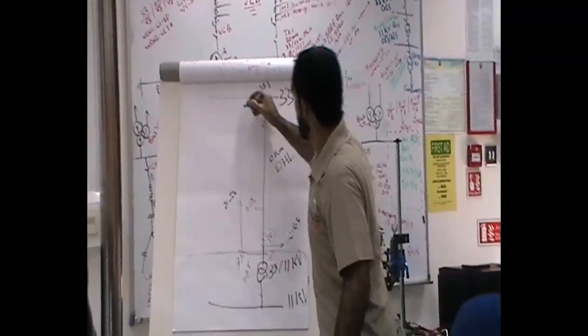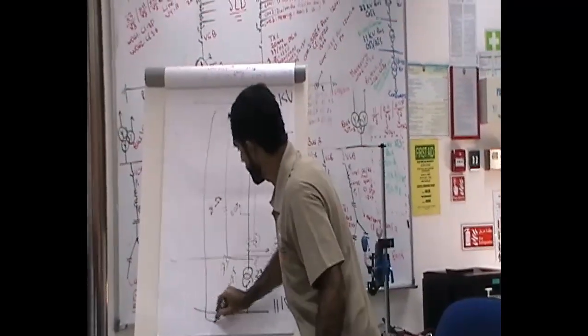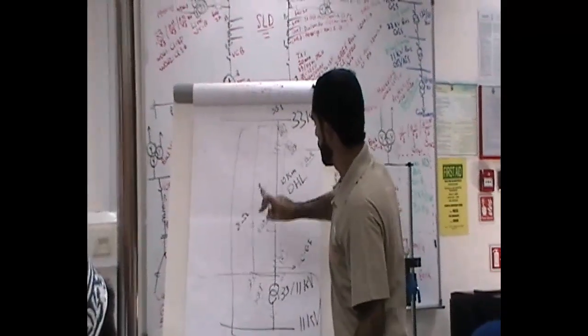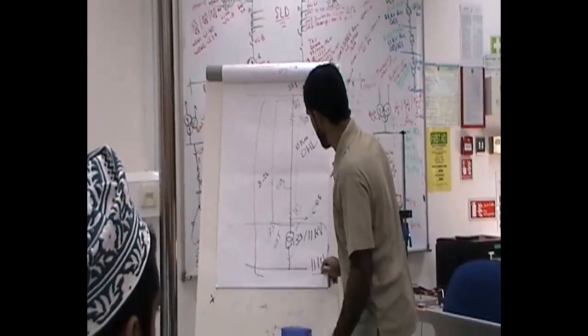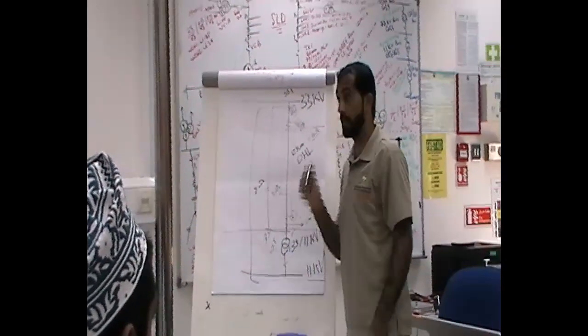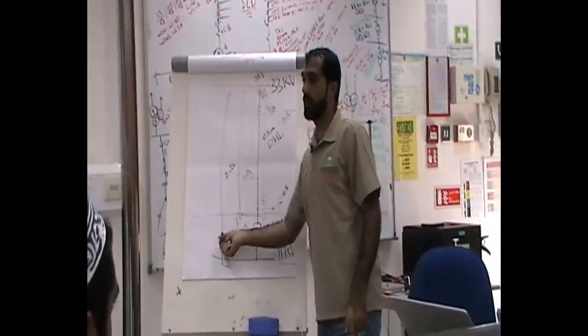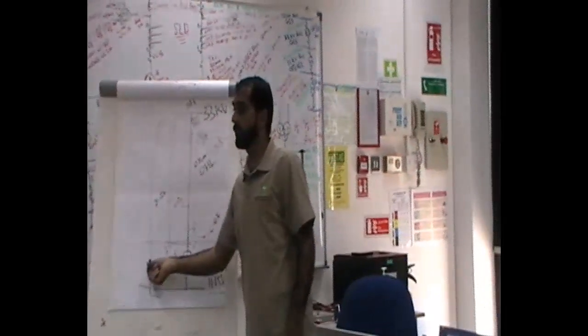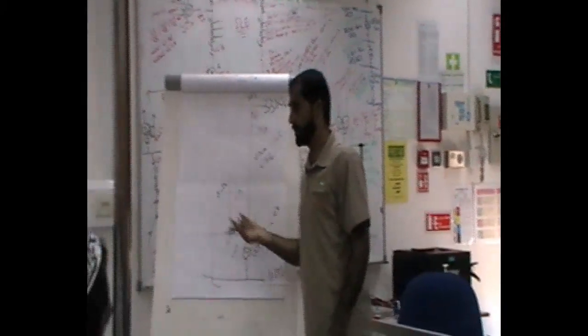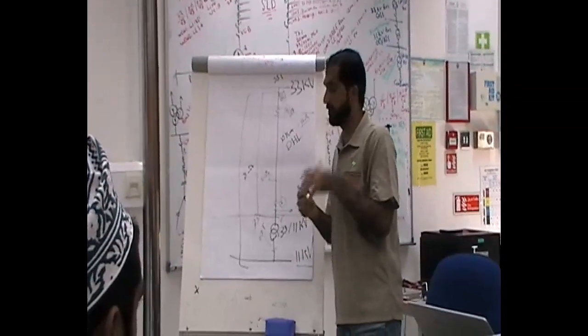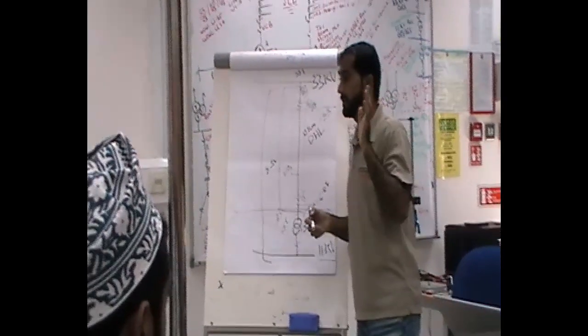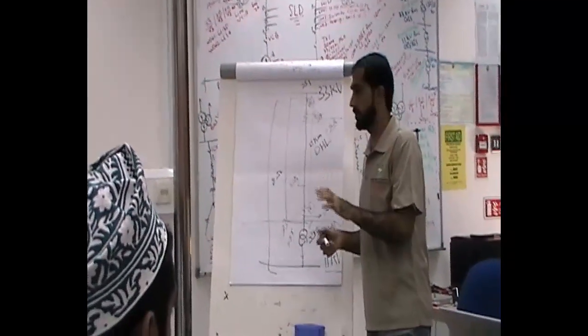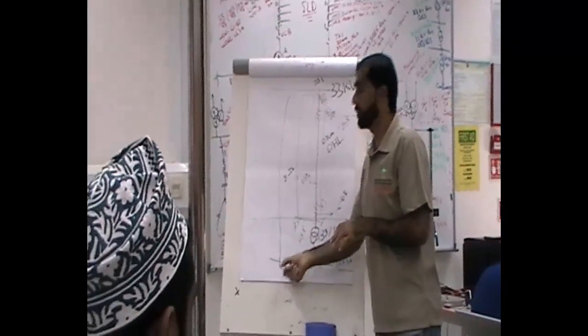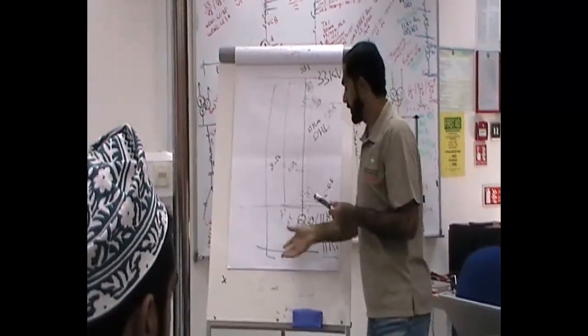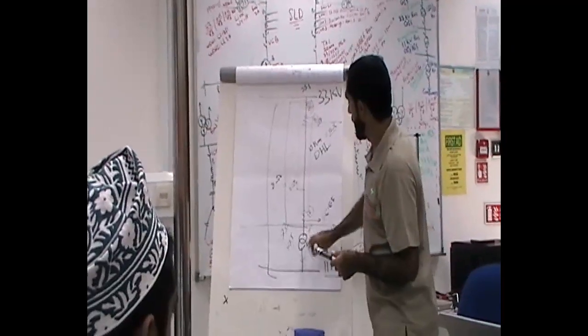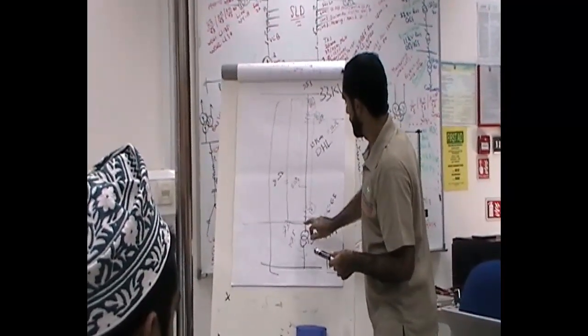120%. Now the last one is zone 3. I'm giving very high setting for zone 3. It will extend up to 11 kV substation. But what was the timing for zone 3? 1.2, very, very high time. In protection, we are talking about 200 to normally 300 milliseconds, even in backup protection. 1 second or 1.2 is very, very high time. I've given it because it's backup for multi-relays.